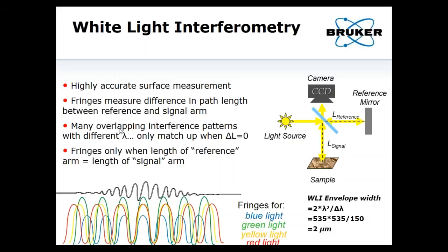With a white light profiler, whereas a laser might have a coherence length of many meters or kilometers, with a white light profiler you have a large bandwidth light source with many wavelengths overlapping. Only at one very unique point in space will all of these wavelengths overlap and combine to give you interference. You have a small envelope determined by the source bandwidth, which is about two microns for us. Only within a two micron path length difference will you actually get interference.